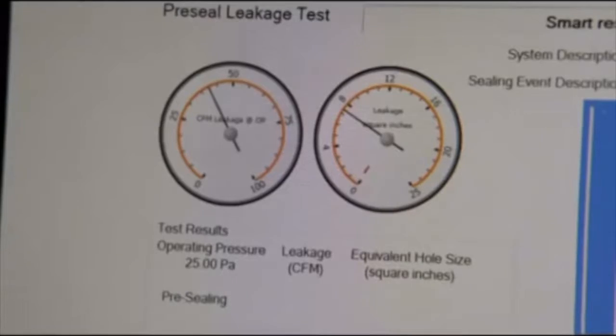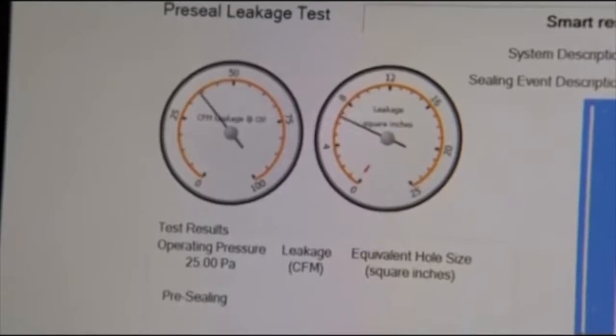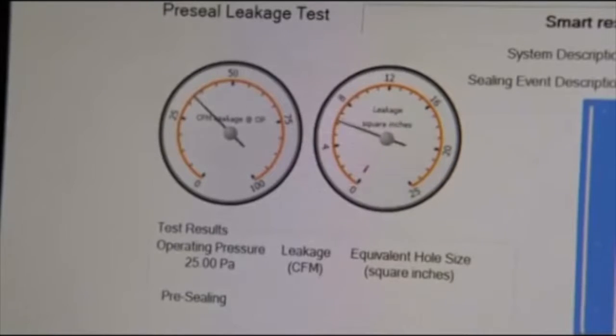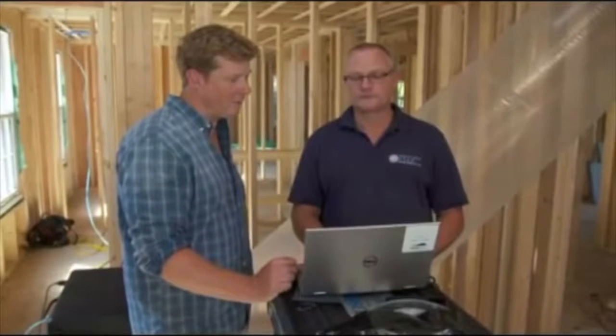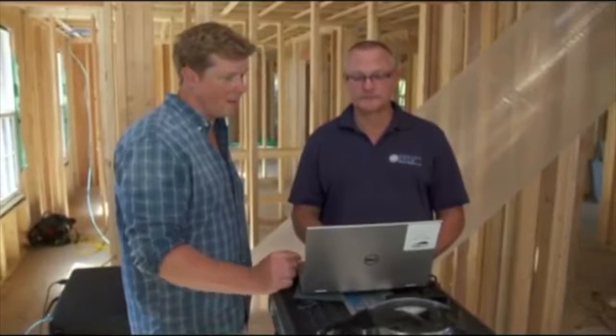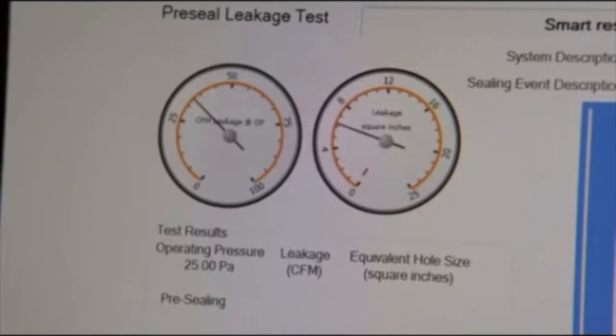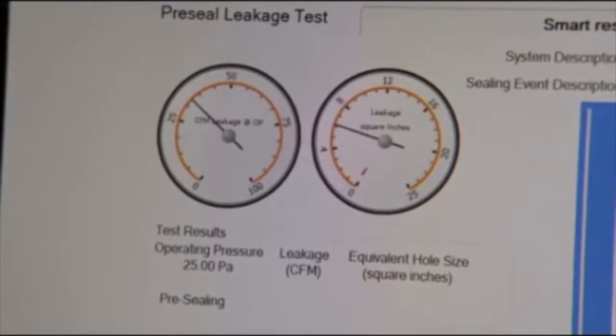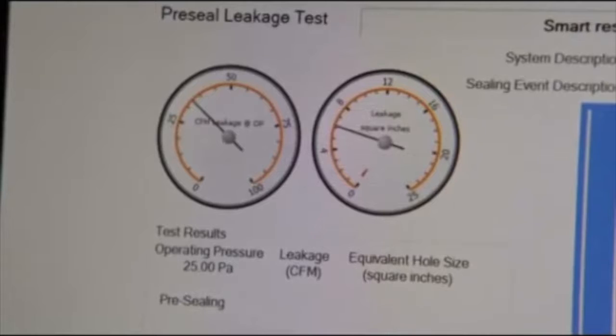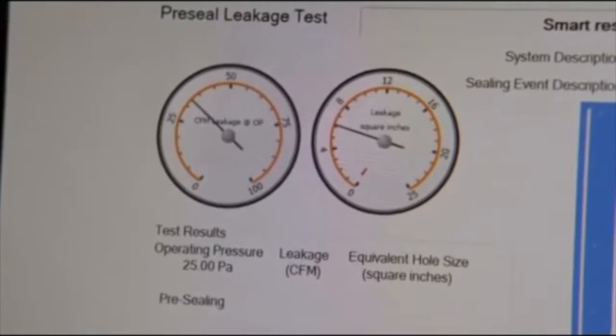So what are the two dials that we're looking at? The dial on the left is telling me, based on the pressure that's in the system, how many CFM, cubic feet a minute of air, is leaking out of the system. And am I reading that correctly, that it's right around 30 CFM? Yes, that's correct. All right. And then this dial? The dial on the right converts that CFM measurement into something you can visualize. So this is leaking about the size of a credit card. So what is that, about 6 square inches? About 6 square inches. And you can improve on that? We can definitely improve on that. Let's plug up all these holes.